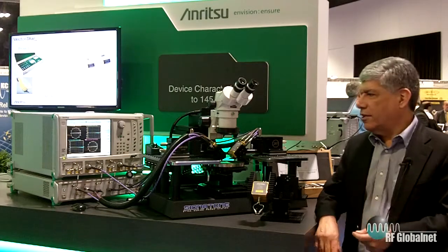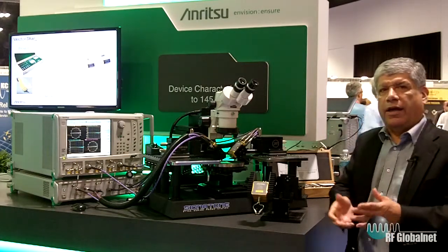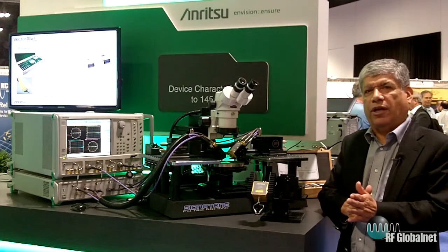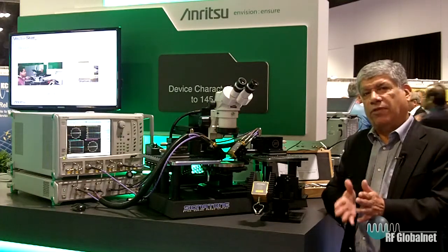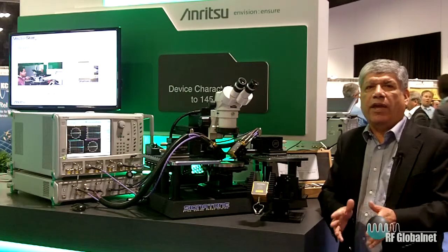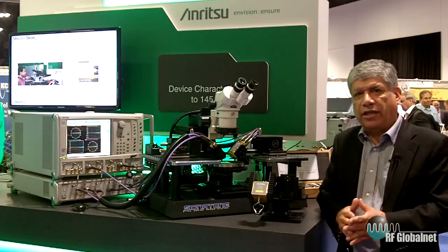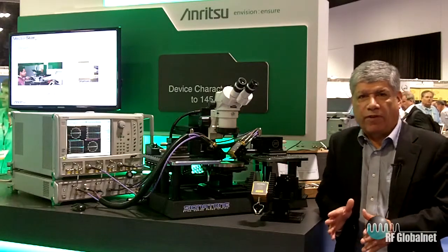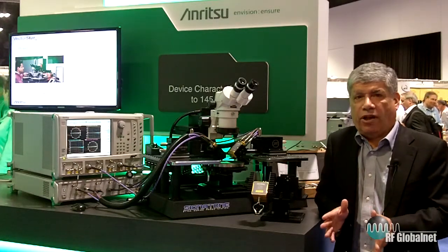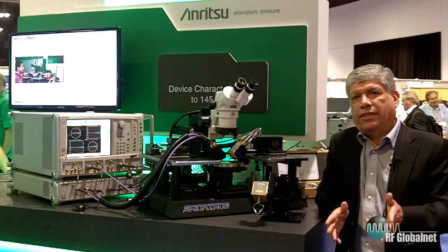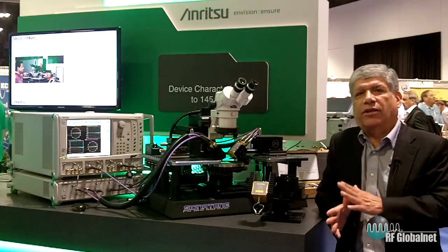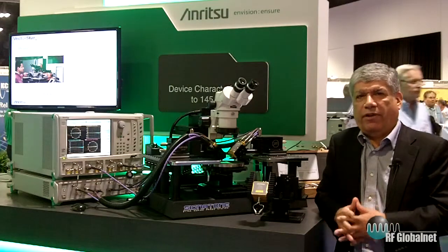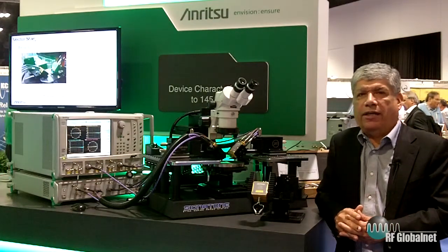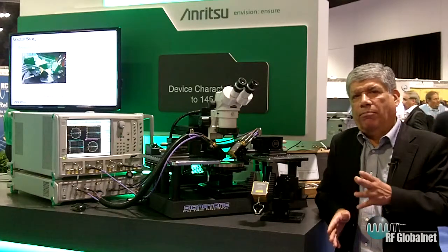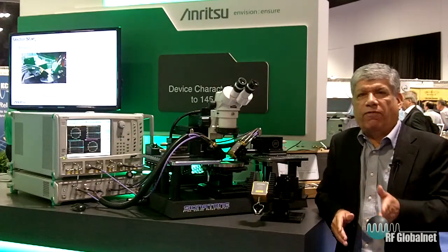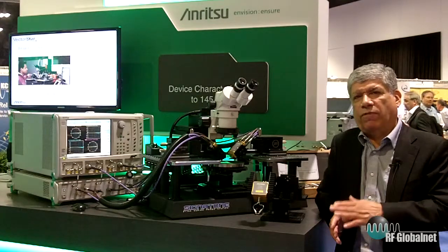And those frequencies are coming to the module and transmitting through the transmission line from 70 kilohertz to actually 54 gigahertz. And then we have our nonlinear transmission line modules that Anritsu develops using the ShockLine technology that propagates and multiplies the signal all the way to 145. The way that we do that is we have multiple bands, multiplier bands, that go from 54 to 80, 80 to 110, and 110 to 145.